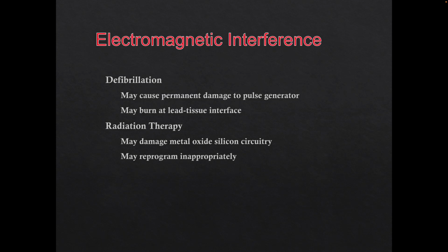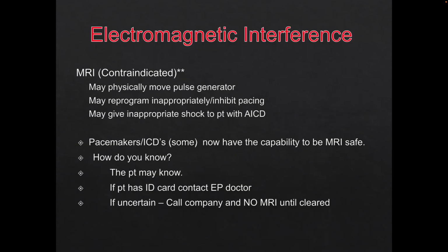Radiation therapy, so don't ever put it on top. It could possibly damage the device. Radiation therapy may also cause issues with the circuitry or reprogram the device. And then I have MRIs. I have MRIs contraindicated with asterisks because it's not always contraindicated. Some people can go for an MRI, but we want to make sure that the patient is cleared for it. The patient may know, but 99.9999% of the time they do not know. They don't even carry their ID cards with them, even though we tell them to.